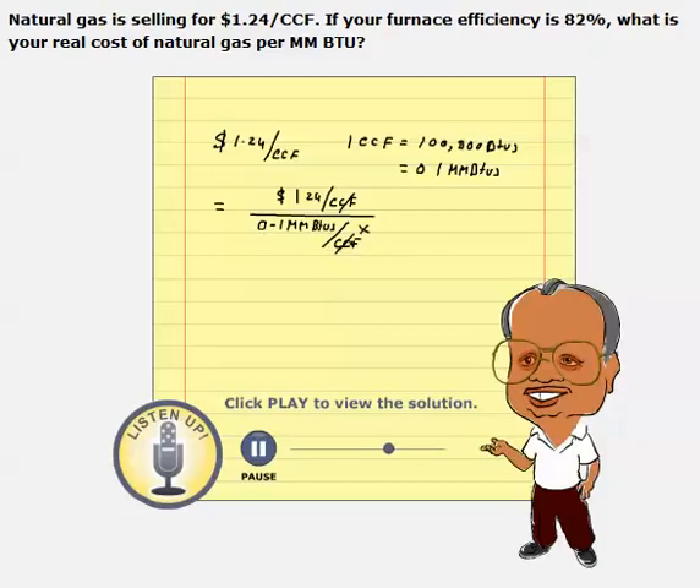Although we buy 0.1 million BTUs, we get only 82% of that heat as actual output because of the efficiency. So we are paying $1.24 and trying to get 0.1 million BTUs, but the furnace gives only 82% of this 0.1 million BTUs. That's the reason we multiply by efficiency here. This is equal to $15.12 per 1 million BTUs.